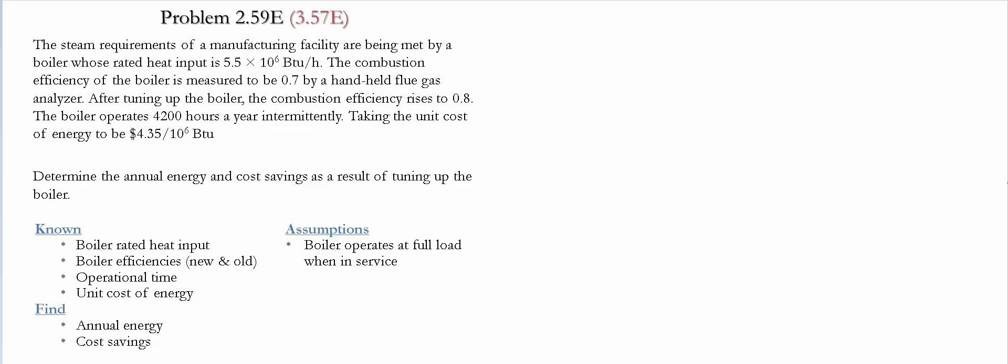The combustion efficiency of the boiler is measured to be 0.7 by a hand-held flue gas analyzer. After tuning up the boiler, the combustion efficiency was raised to 0.8. The boiler operates for 4,200 hours in a year.